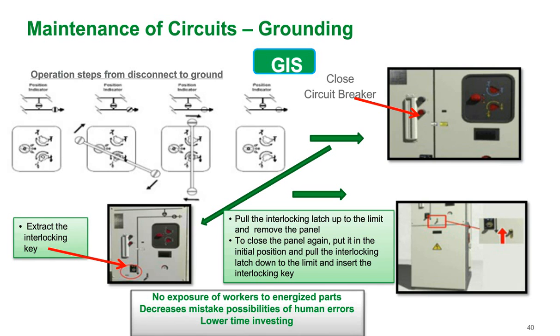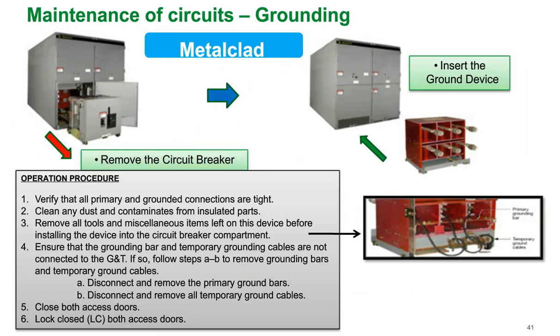Of course, with metal clad, if you're racking in a grounding device, you have a door open. Even with arc-resistant metal clad, you still have to open a door in order to rack in a grounding device. So you're still exposed potentially to some live parts. So from a safety perspective and also a simplicity perspective, you can see the advantage of having an integrated grounding switch in GIS versus a rackable grounding device in air-insulated switchgear.